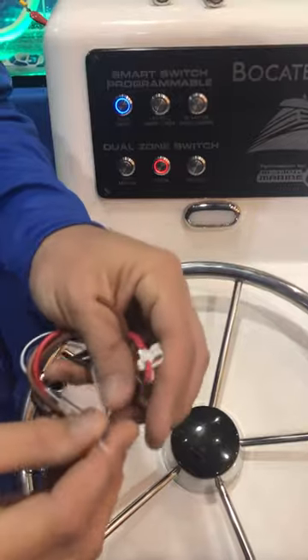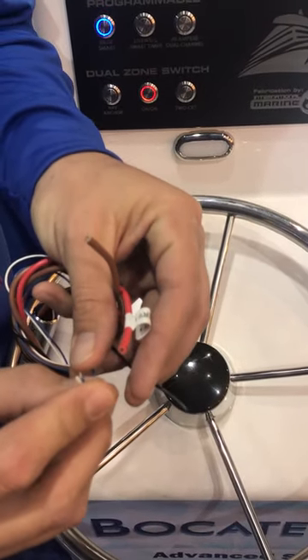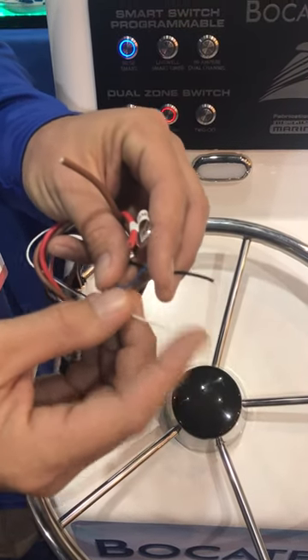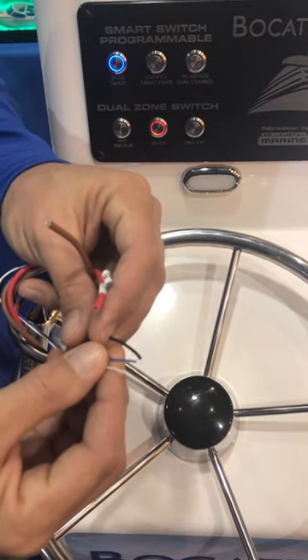Our smart switch is programmable to set user-defined amperage settings. Cap off both leads for 20 amps. Cap off lead 2 and ground out lead 1 for 15 amps. Ground out lead 2 for 10 amps. Ground out both leads for 5 amps.